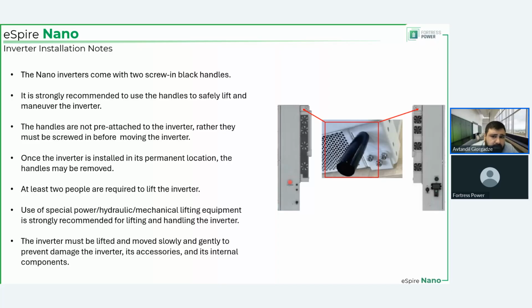In our case, for example, we managed to raise it and put it on the wall mount bracket using an engine hoist. We had one random one laying around in the lab, and that did the job perfectly fine. Obviously, you handle this inverter with care. You don't want to drop it. You don't want to hit it against anything. Be gentle with it. Yes, it's solidly built, but it's just a human-made object that can be damaged just like anything else, especially considering that it has this dongle sticking out here. It has the EPO button sticking out on the other side. It has the DC switch right here. It has plastic caps on the bottom instead of the metal knockouts. And as I said, it's 200 pounds. Even if you drop it a couple of inches above the ground from that height, you'll still manage to bend it.